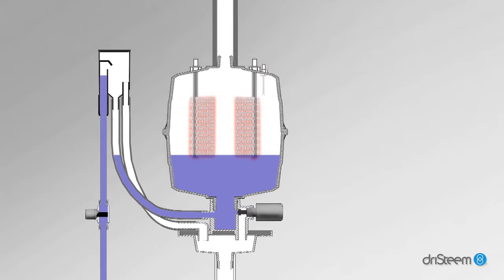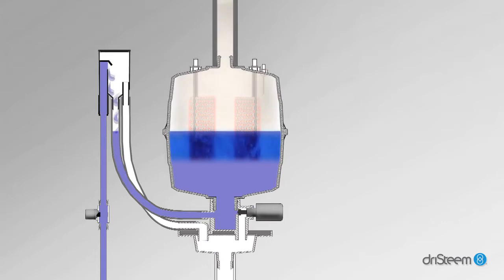If there is not enough electrical current between the electrodes, the fill valve opens and water enters the steam cylinder. As the amount of water covering the electrodes increases, electrical resistance in the water causes it to heat up and boil into steam which is discharged into the airstream.